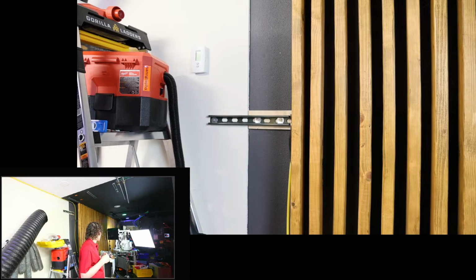So all of those will turn off, and the DC power supplies on this unit are not water cooled, so it doesn't have to turn the whole microscope off. It just turns off optics and stage and that stuff. And the turbo pump doesn't need to be water cooled most of the time. It only needs to be water cooled when you're doing plasma cleaning or it has a really high gas load. So it's fine if it loses cooling, because most of the time you're not plasma cleaning.